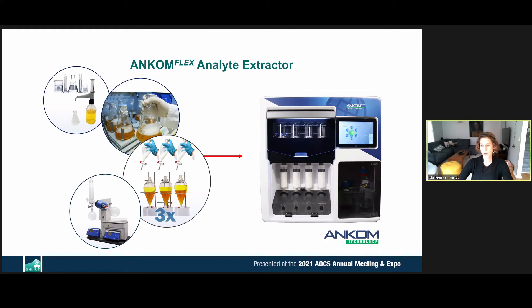The software on this automated instrument, called ANKOMFLEX, is modular. You can combine any method that requires a digestion in the upper portion, filtration and mixing in a nitrogen environment in the middle, and evaporation of solvent at the bottom.